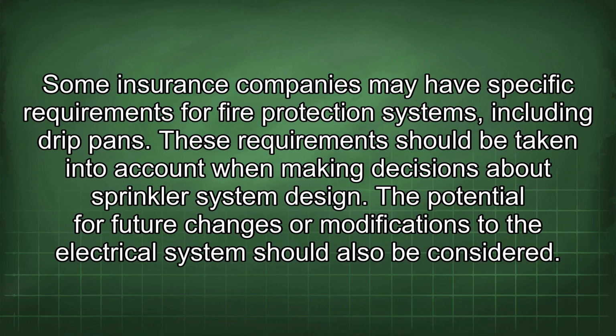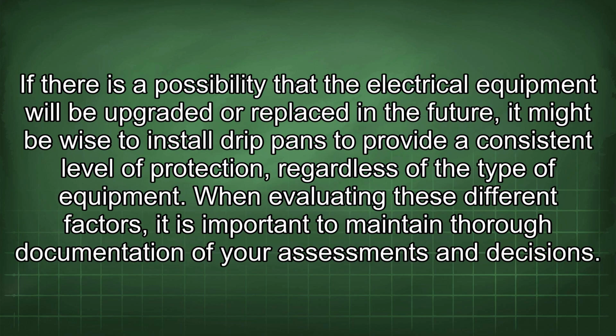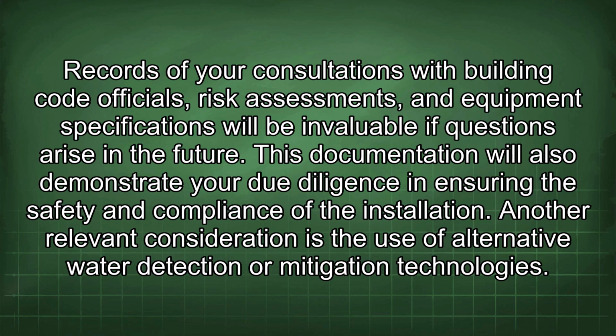The potential for future changes or modifications to the electrical system should also be considered. If there is a possibility that the electrical equipment will be upgraded or replaced in the future, it might be wise to install drip pans to provide a consistent level of protection, regardless of the type of equipment. When evaluating these different factors, it is important to maintain thorough documentation of your assessments and decisions. Records of your consultations with building code officials, risk assessments, and equipment specifications will be invaluable if questions arise in the future. This documentation will also demonstrate your due diligence in ensuring the safety and compliance of the installation.